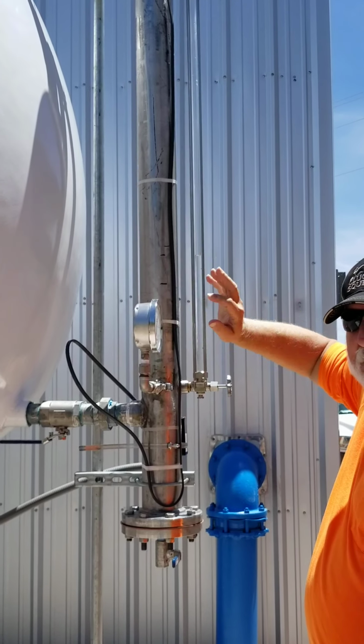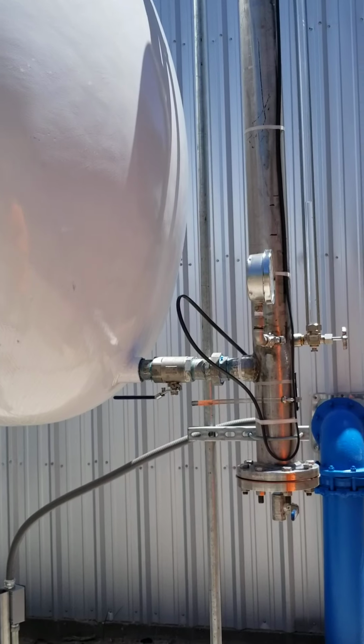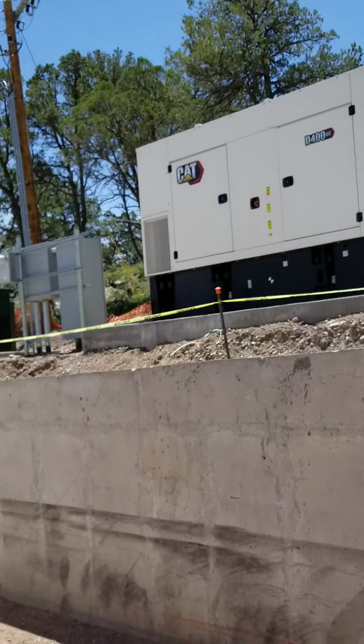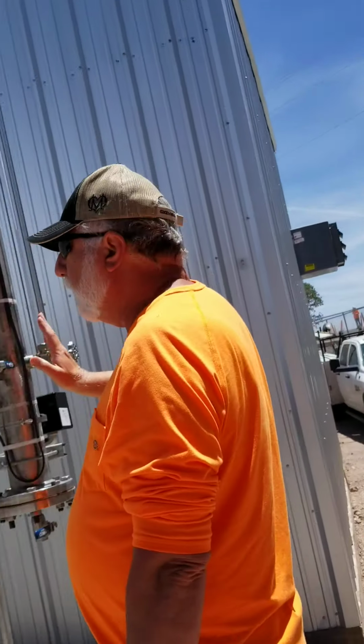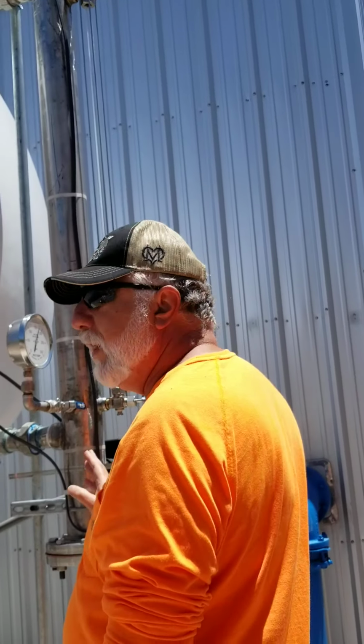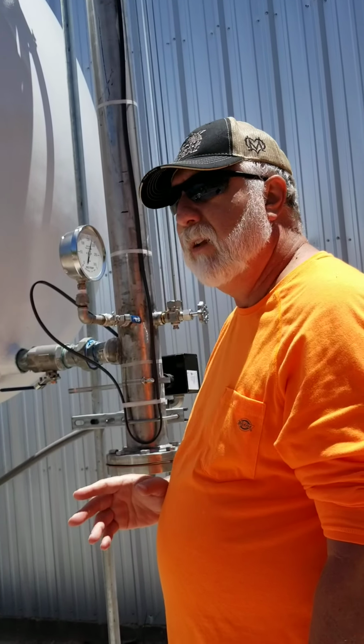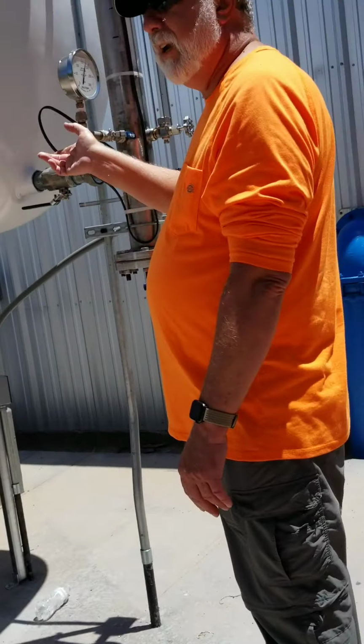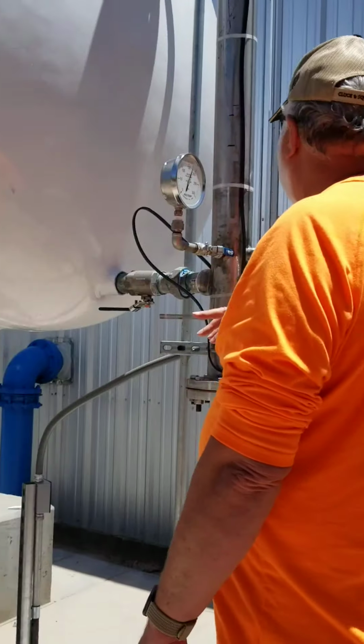So rather than reading a clear sight tube in the building or something, where you customarily see them, everything's mounted here. We do that for multiple reasons. We do have it on the HMI screen also that shows those. Yes, you will see on the HMI screen if the probes are activated or not.